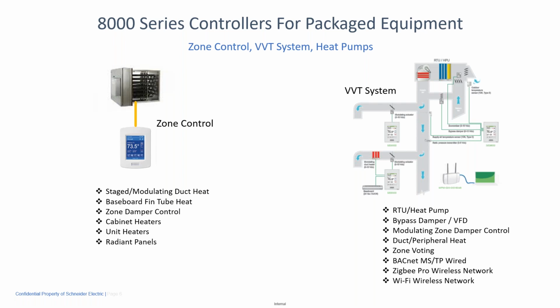There's also an option for these guys to do a VVT system, right? So I can have one controller control a rooftop unit and bypass or VFD, and then units for each one of the zones that get a vote. X number of votes causes the unit to create heat. The rooms that need heat, damper opens up. The rooms that don't need heat, damper closes down and then goes back to normal operation with just the fan.